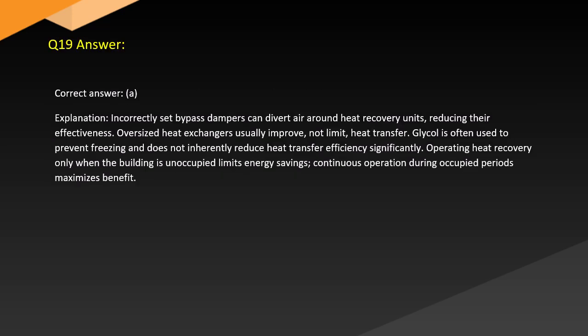Answer. Correct answer: A. Explanation. Incorrectly set bypass dampers can divert air around heat recovery units, reducing their effectiveness. Oversized heat exchangers usually improve, not limit, heat transfer. Glycol is often used to prevent freezing and does not inherently reduce heat transfer efficiency significantly. Operating heat recovery only when the building is unoccupied limits energy savings. Continuous operation during occupied periods maximizes benefit.